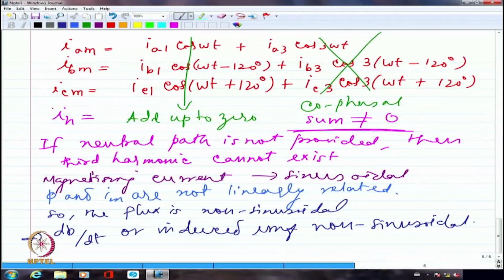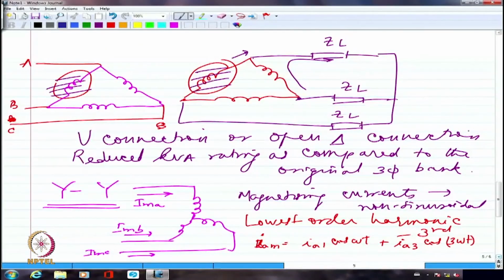So I would not like to normally use a star-star connected transformer without the neutral being grounded, unless I provide some path for the third harmonic current. If I want to provide the path without connecting the neutral, right, I might like to have a tertiary winding in delta. It can very happily have a circulating current, who cares? If I have a secondary winding or a tertiary winding in delta, secondary winding already I said is star, star, star. So I can have a tertiary winding in delta. So sometimes the tertiary winding serves this purpose in a transformer. If it is a three-phase transformer, star-star connected, without neutral grounding, there can be a tertiary winding connected in delta, which can simply circulate the third harmonic current.